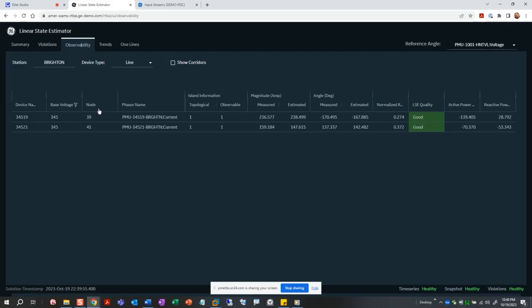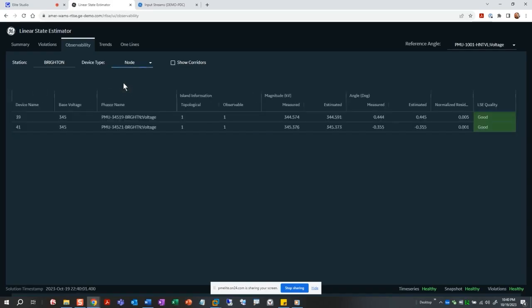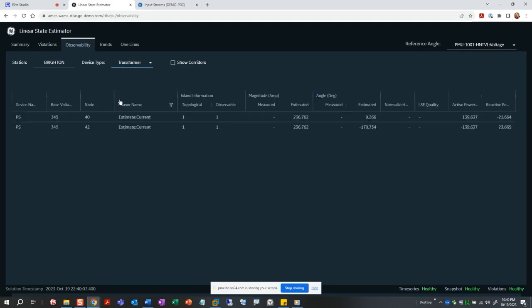We want to look at the observability on the system. So at Brighton here, we've got some measured currents on the system on our transmission lines. We're also going to look at the measured node voltages on our Brighton substation. And then we've got some transformers. So on all of our transformers, we're estimating the currents through the transformers in this demo system.